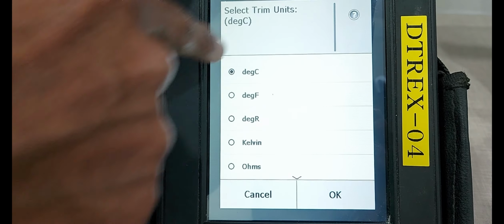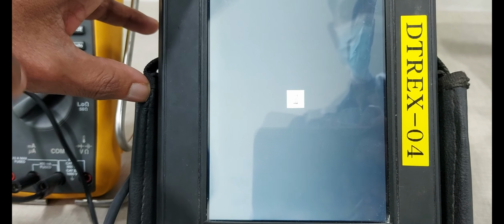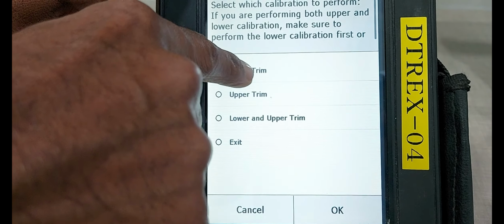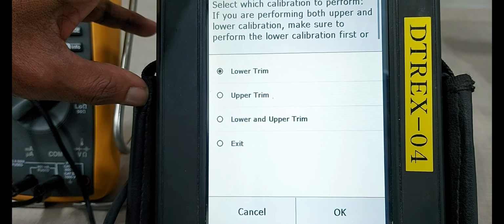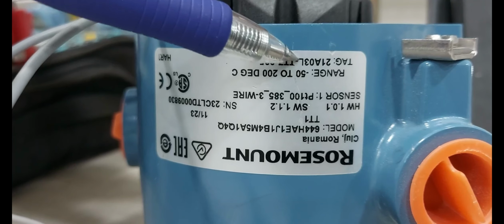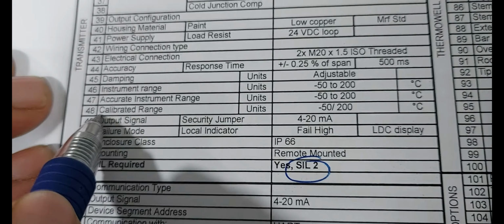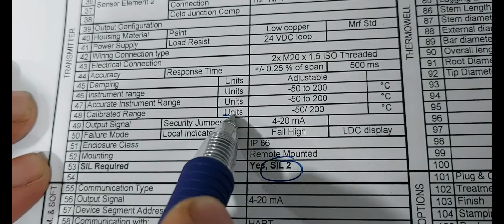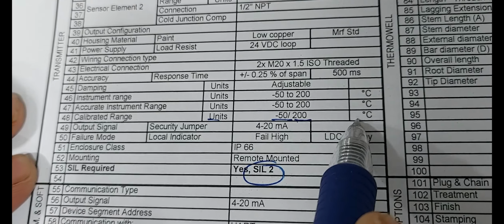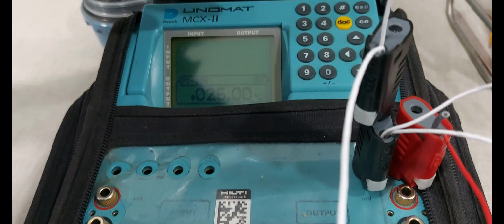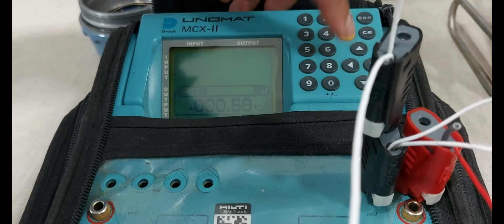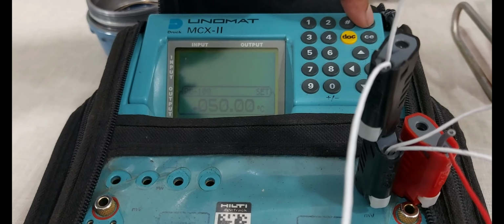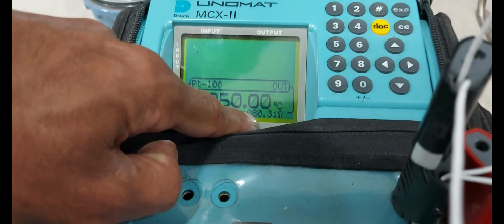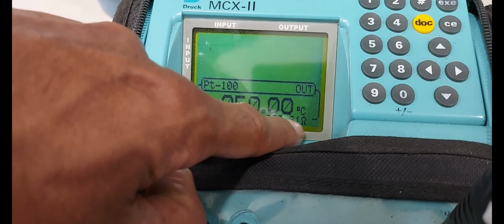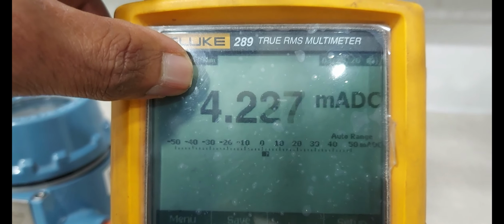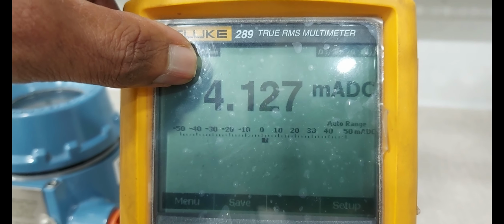Select the temperature unit, select the temperature degree. First we are performing the low sensor trim. Instrument calibration range -50 to 200 degree, as per the data sheet. First we are applying -50 degree and enter. The corresponding resistance value showing 80.31 ohms. Now milliamps approximately 4.1.